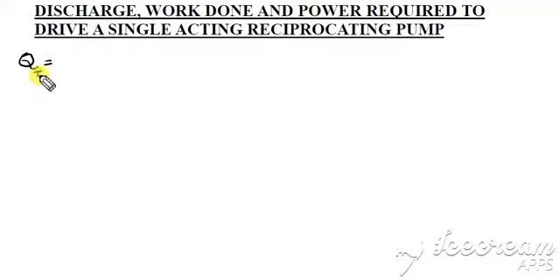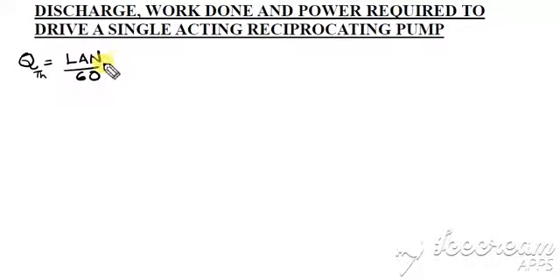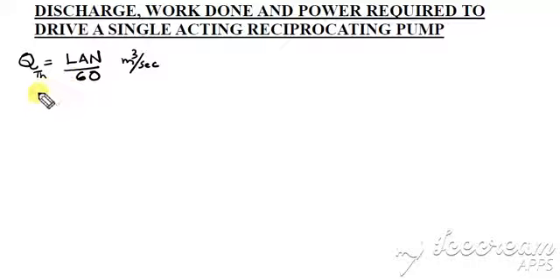We have already found the discharge expression for a single acting reciprocating pump. The theoretical discharge Q is equal to LAn/60, where L is the stroke length, A is the area of cross section of the piston or cylinder, and n is the rotational speed of crank in RPM. In SI units, the unit of discharge is cubic meters per second. For a double acting pump, it is approximately twice this value, that is 2LAn/60.